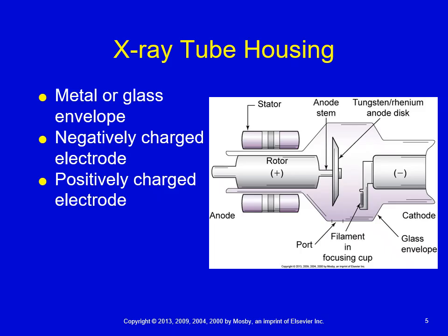The only thing that keeps them from going in all directions is the fact that it is enclosed with that lead enclosure. Now, I'm not going to say it keeps it from going in all directions, but it keeps it exiting from all directions because that lead actually blocks the X-rays from getting out, with the exception of the leakage radiation.